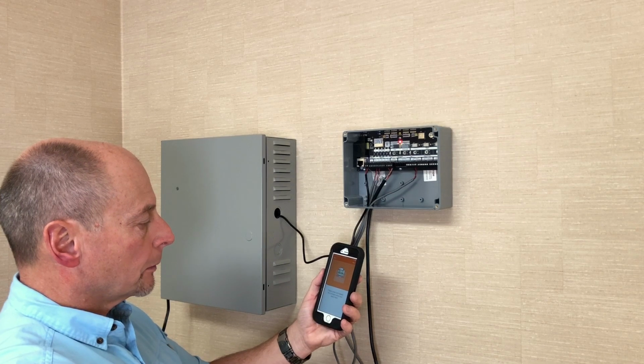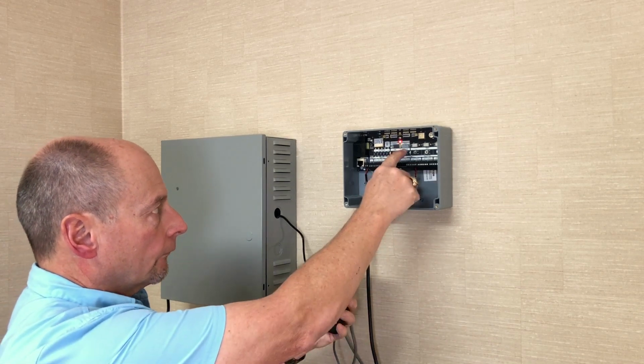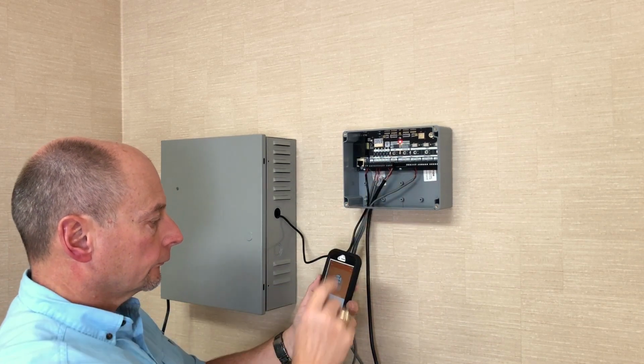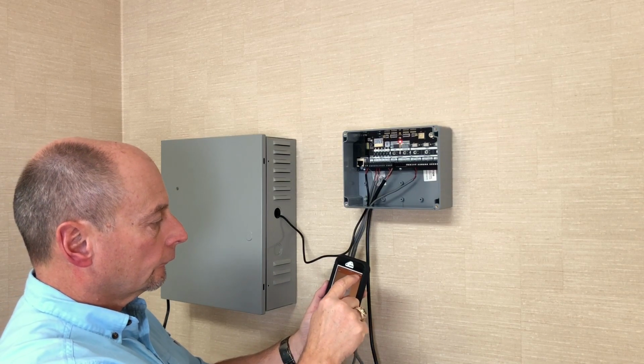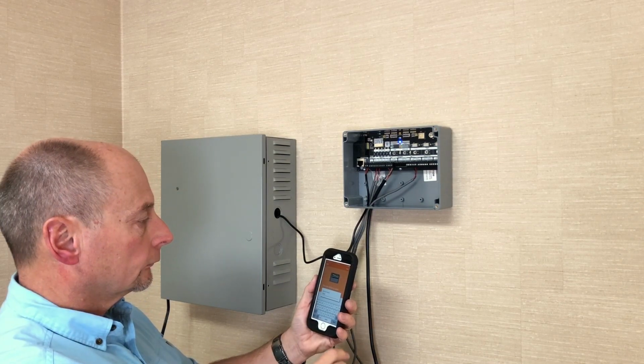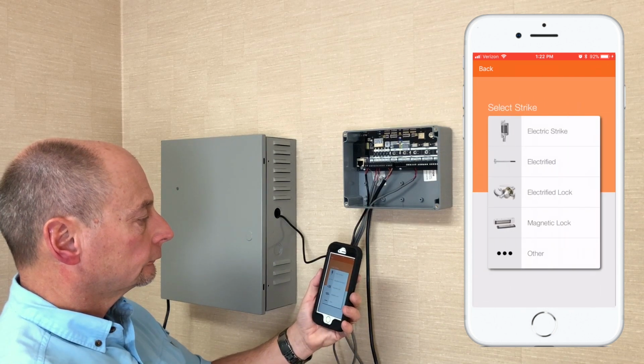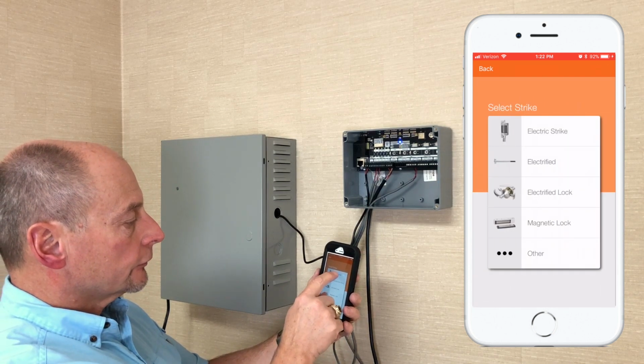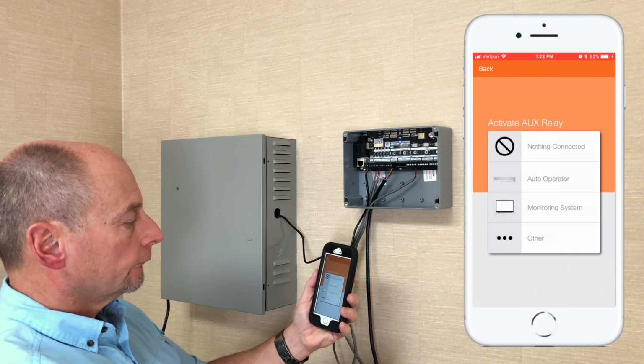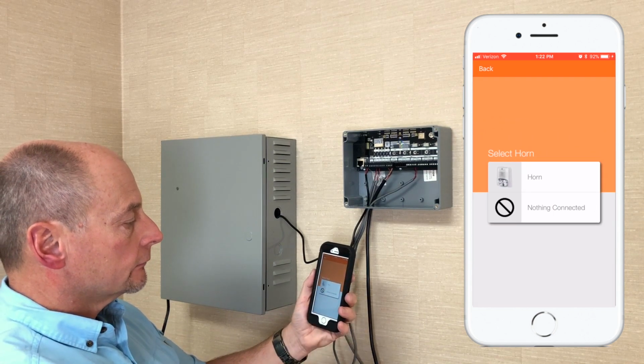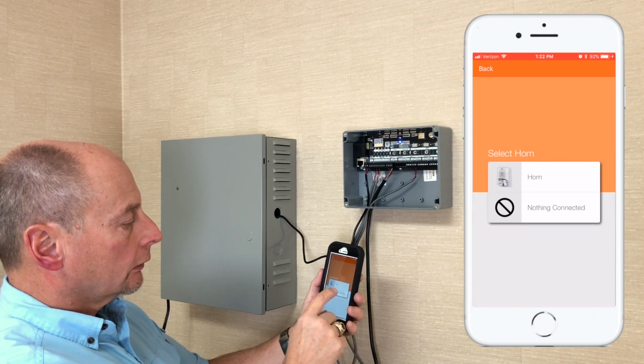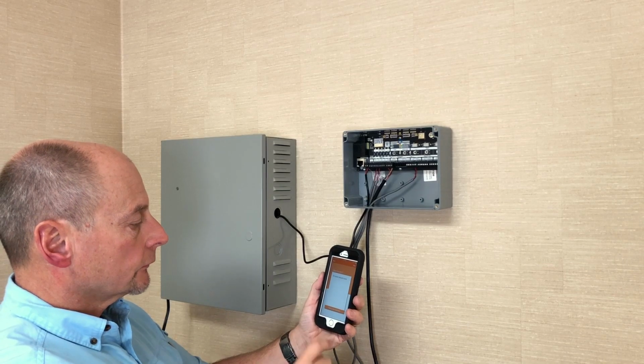Once the CTE is installed and connected, use the Engage mobile app to commission the CTE to your Engage account. During commissioning, be sure to select the appropriate options for your relay outputs. The lock, alarm, and aux relays must be configured during commissioning. See the user guide for more information.